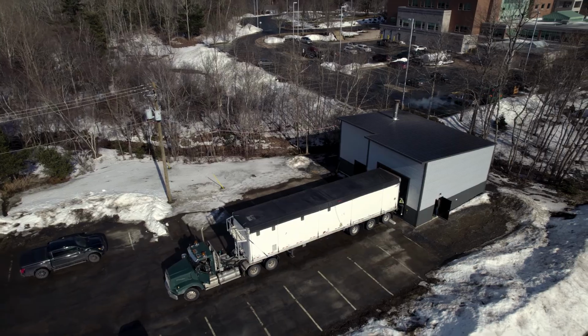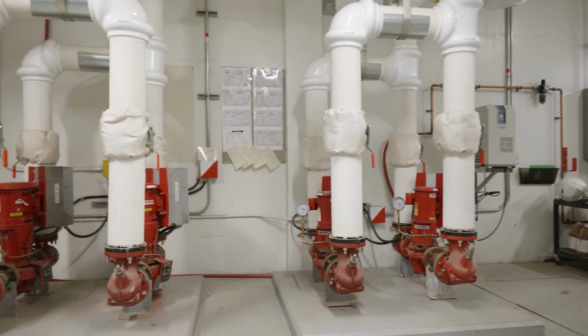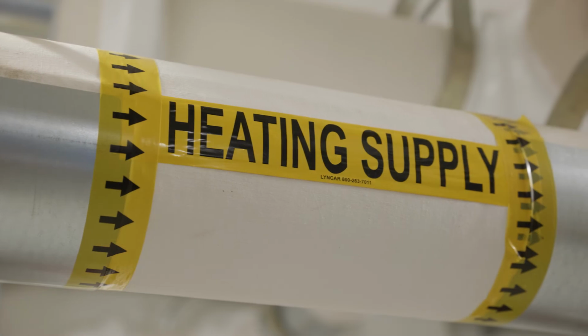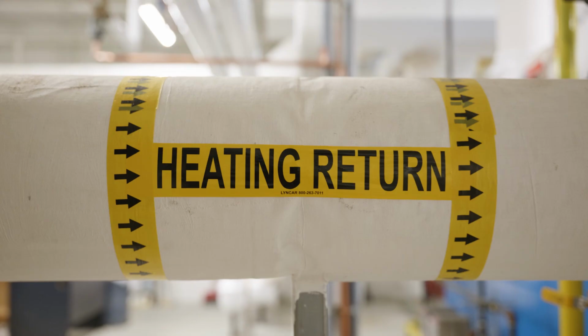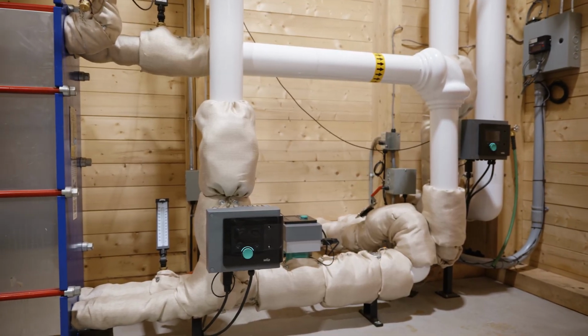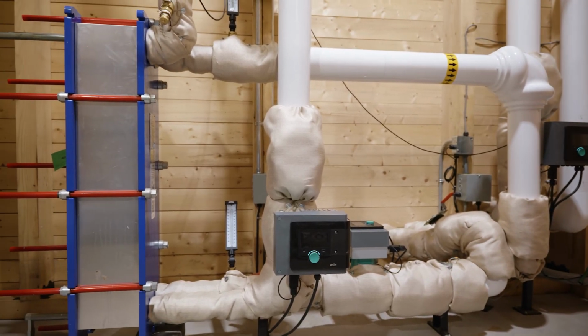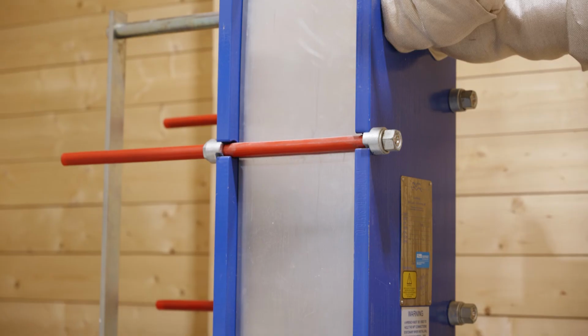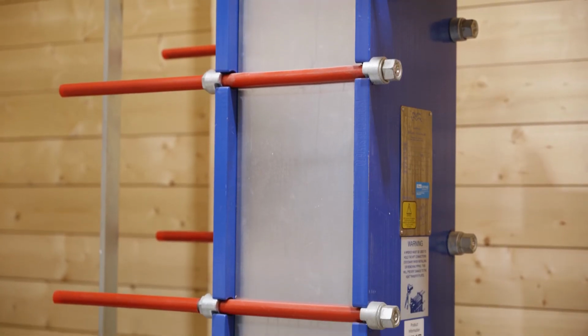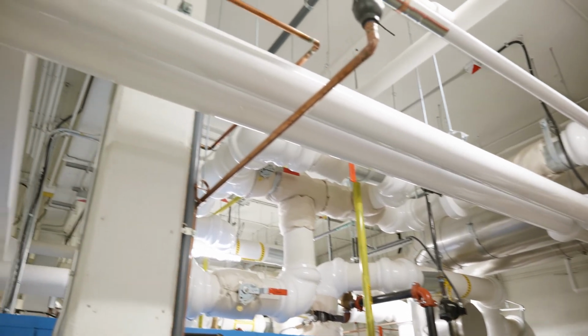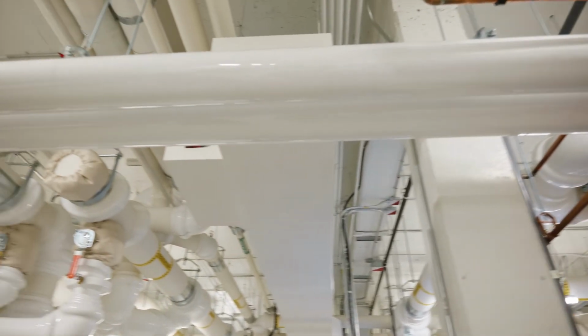So the tie-in to a biomass system is very simple. All the boilers already in the facility stay as is. Nothing changes except we simply tie into the supply and return water of their system. We did that in 48 hours with minimal disturbance. There's no mixing of water from our system to theirs. We're just heating one side of the heat exchanger, and through that heat exchanger they're supplying and return on the other side.